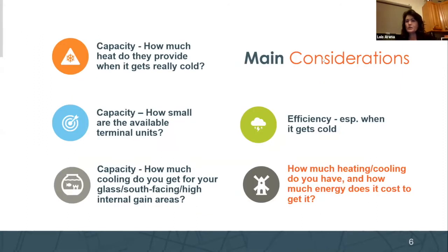So the main considerations when you're looking at these systems are, do they have the capacity that you need? Can they supply the heating you need in really cold climates, right? We have what's called cold climate heat pumps, cold climate VRF systems. You want to make sure you're looking for that in cold climates. Capacity, actually, how small can we go? Because we all know our passive house projects have super low heating loads. What's the smallest unit we can get for the terminal units inside the project? And then can we get enough out of that same unit for cooling, right?